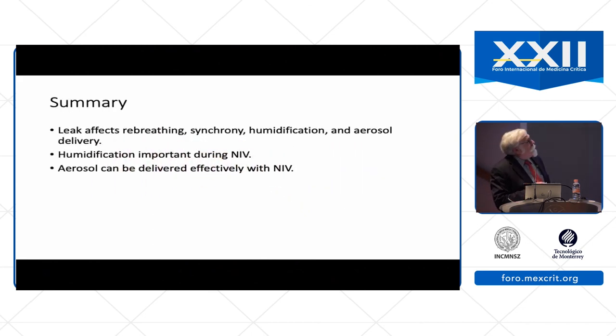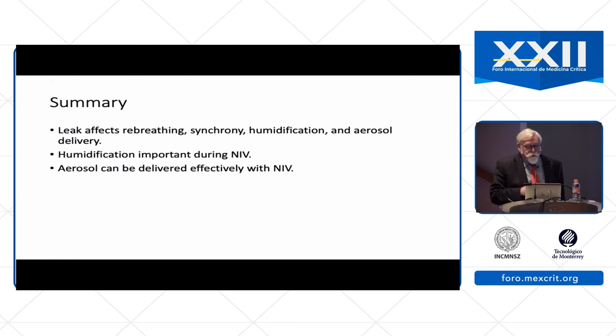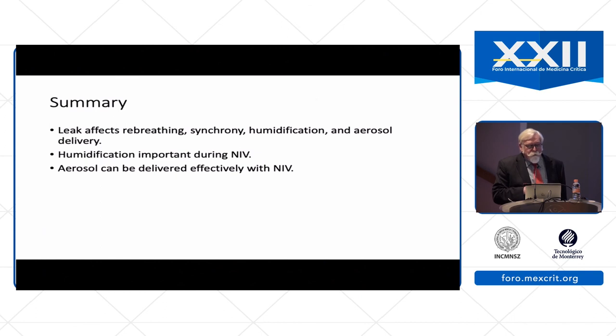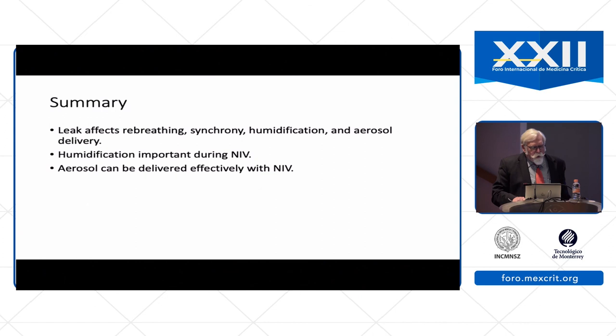In summary, leak during non-invasive ventilation affects re-breathing, synchrony, humidification, and aerosol delivery. Humidification is important during non-invasive ventilation for patient comfort, and aerosols can be effectively delivered during non-invasive ventilation. The key point is that with invasive ventilation, the nebulizer goes at the outlet of the ventilator, while with non-invasive ventilation, the nebulizer goes at the position of the mask. Thank you for your attention.